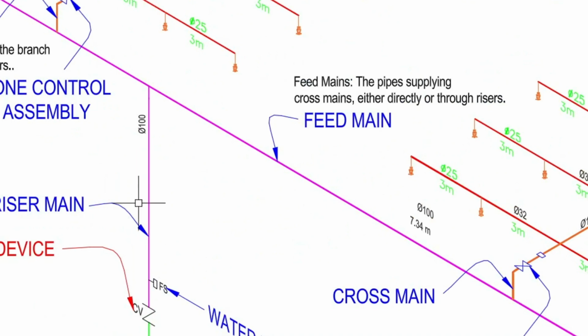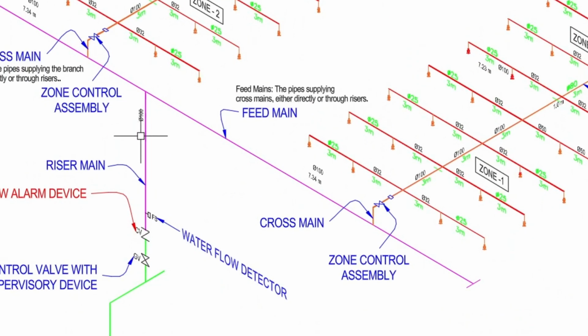Hello friends, in this video we will see what is an alarm check valve, why do we need an alarm check valve and its components. This sprinkler system we discussed in some videos. See, these are all branch lines and these are all sprinkler heads. Then we have cross main, feed main, and all is feeding to one riser main, the vertical pipe. Now one component is there which is called water flow alarm device.